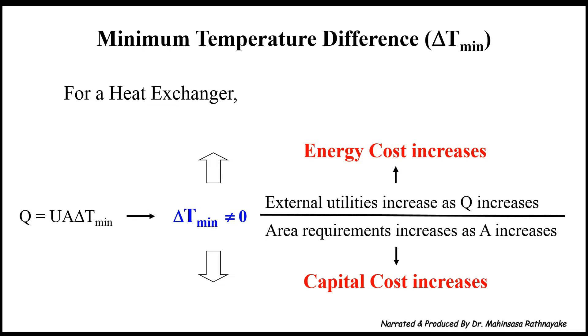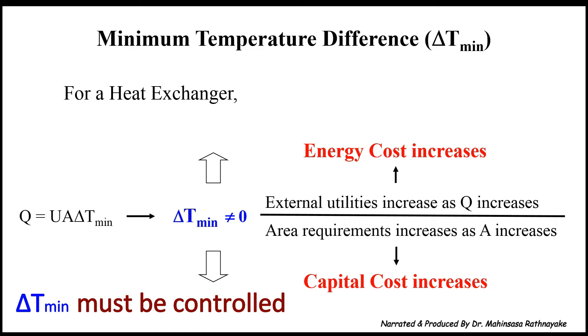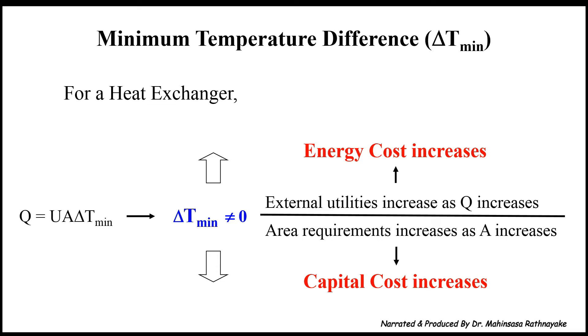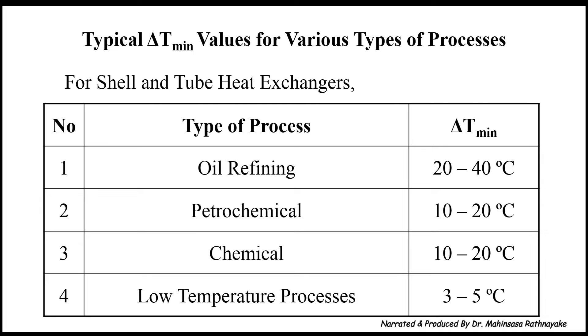When delta T minimum increases, this causes energy cost to increase. On the other hand, when delta T minimum decreases, the area of the heat exchanger increases to maintain the heat duty, meaning capital cost of the equipment increases. Therefore, delta T minimum should be kept at a certain value to compromise between energy cost and capital cost. For various types of processes, delta T minimum is taken by experience. For shell and tube heat exchangers, the typical delta T minimum values for various types of processes are indicated in this table.